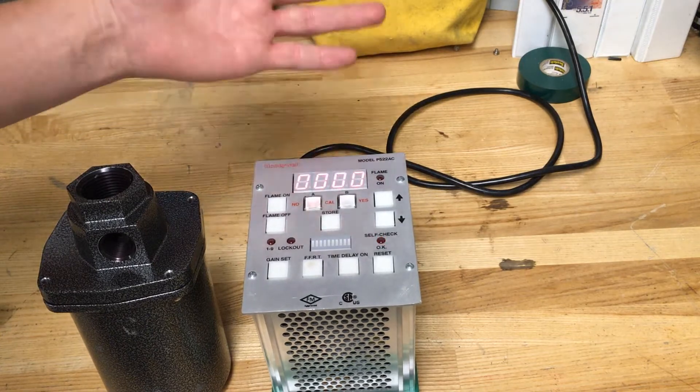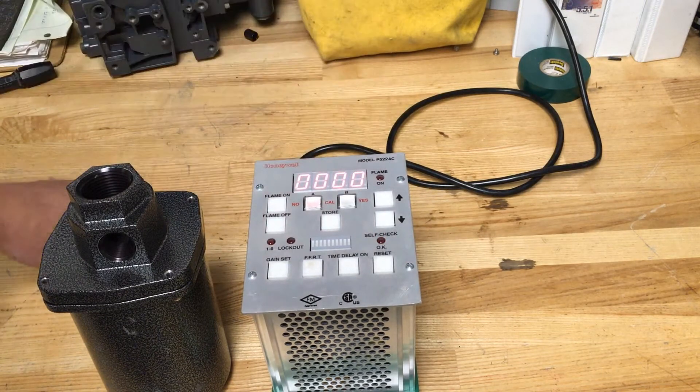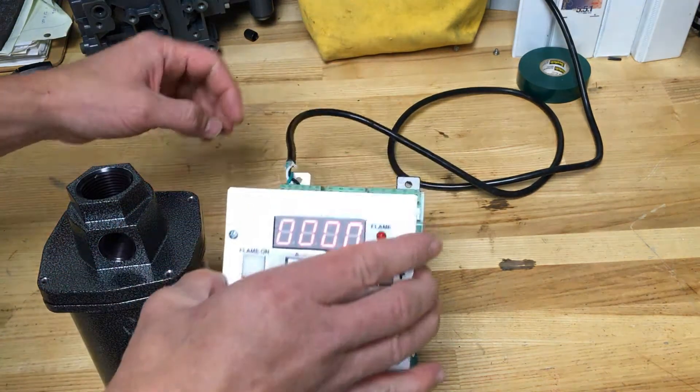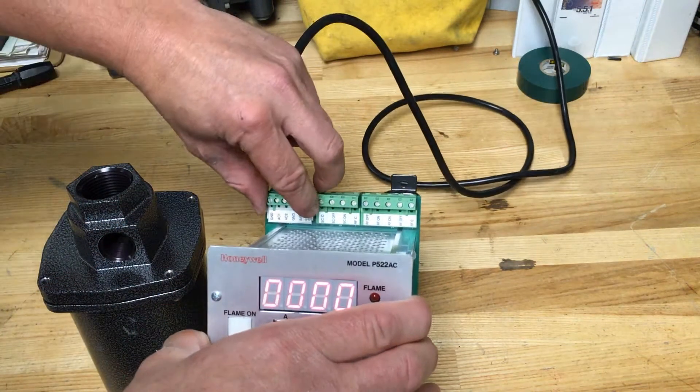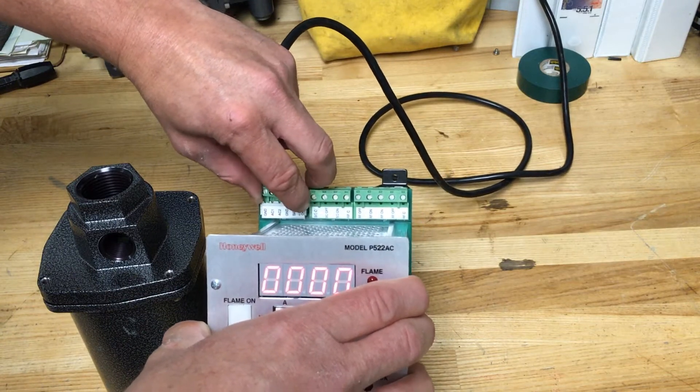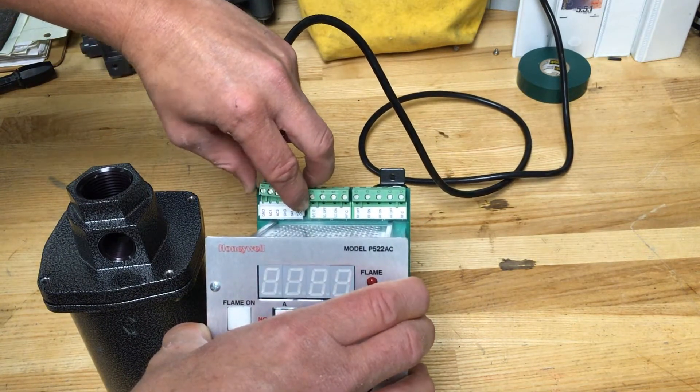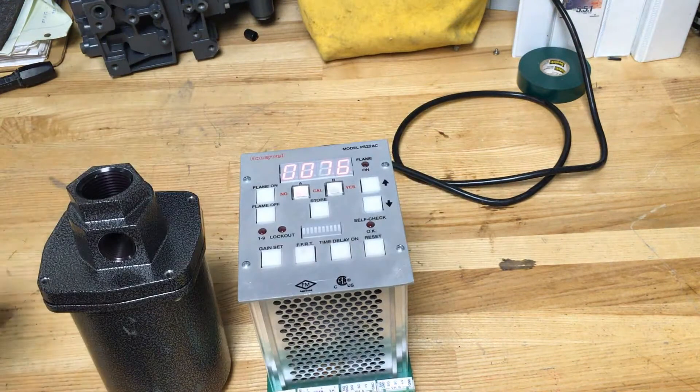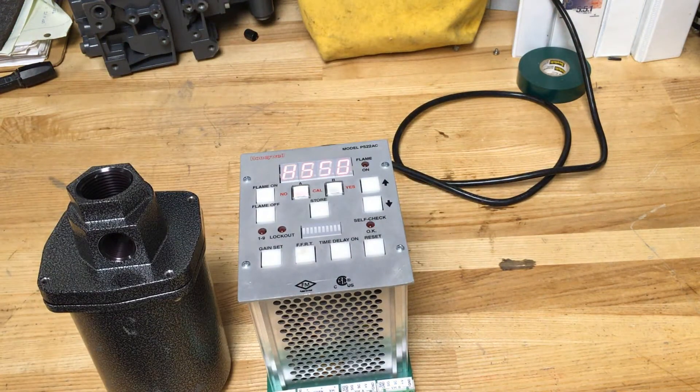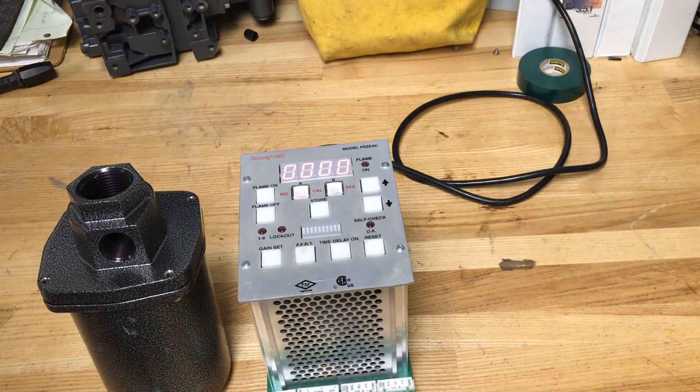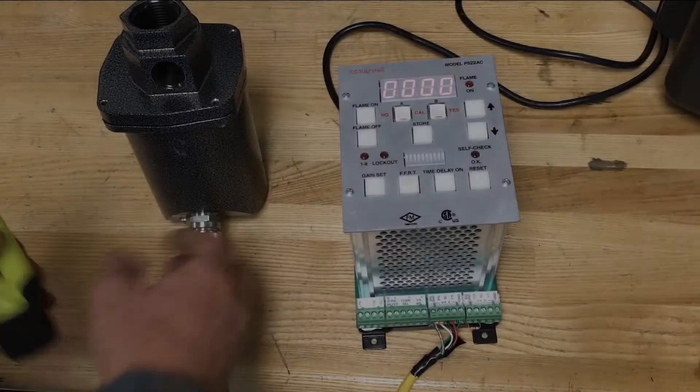It's important to note that every time you connect a head the processor must go through a power-up to establish communication with the viewing head. It is best to remove power to the processor before connecting a viewing head.